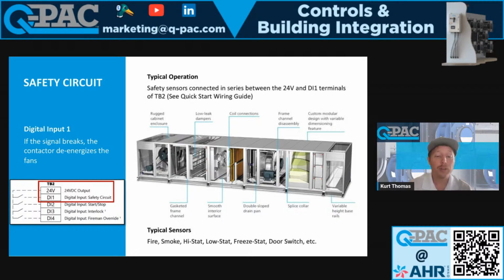If you're afraid that your facility folks might touch a blade or harm themselves, then you can add a door switch. The safety circuit is a hard safety circuit, meaning it kills power to the fan. So we have a contactor in our control panel. If that safety circuit trips, then the fans do not have power. So that is the reason hand mode does not work when the safety circuit trips.